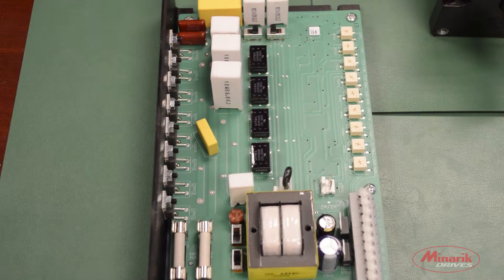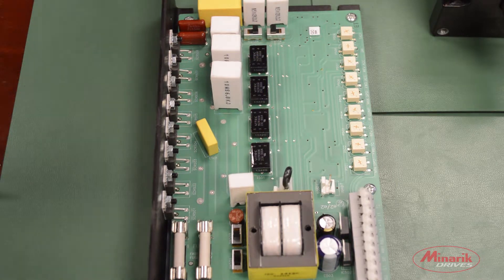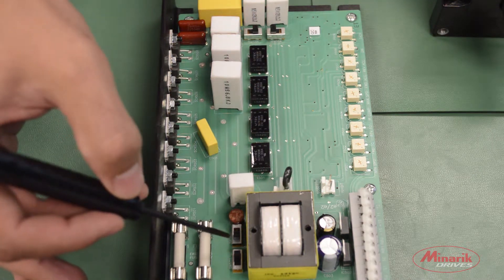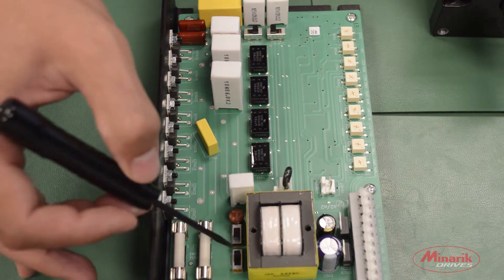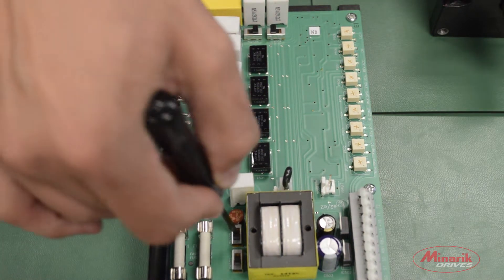The first step to wiring up this drive is to set the input and output voltage switches. The input voltage switches are located next to the transformer and are factory default set for 230 volts AC. We're going to be using 115 so we'll switch both of them to the 115 position.